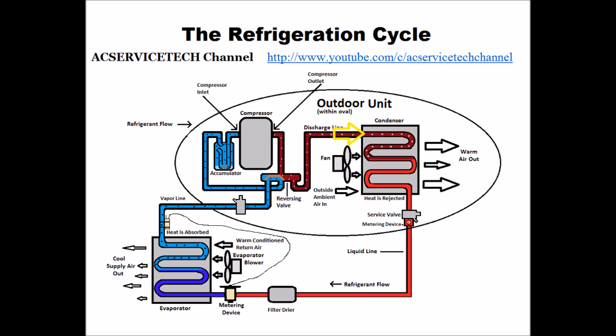It then rejects heat. It continues to reject heat and lower in temperature until it turns into the saturated state where liquid and vapor both exist at the same time. It then turns into a complete liquid, and continues to reject heat, lowering the temperature of the liquid refrigerant until it comes out at the service valve. The temperature decrease in liquid form — between right where it turns into a liquid and all the way down to the service valve — is called the sub-cooling.